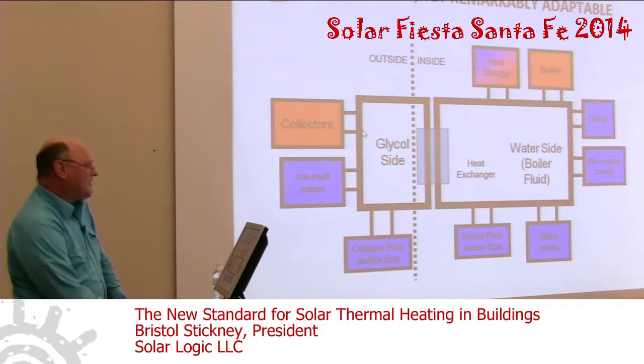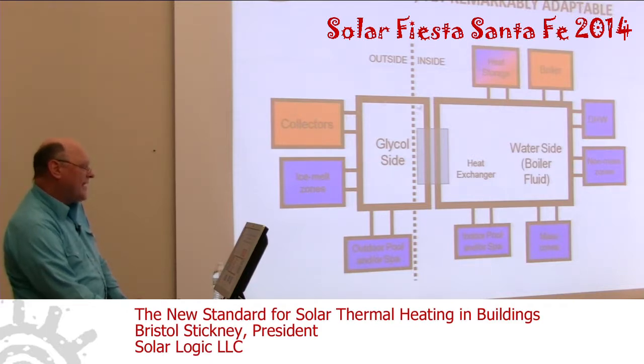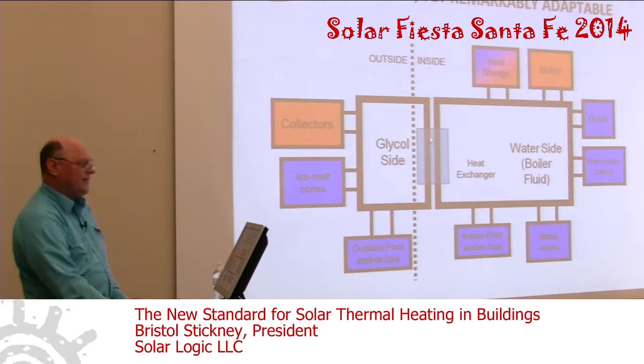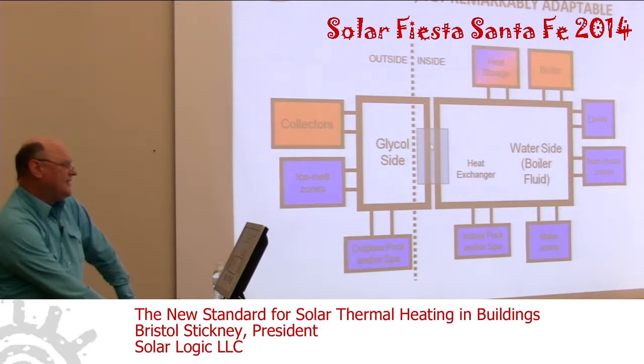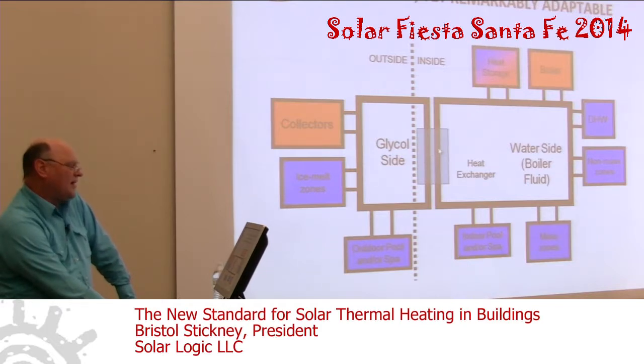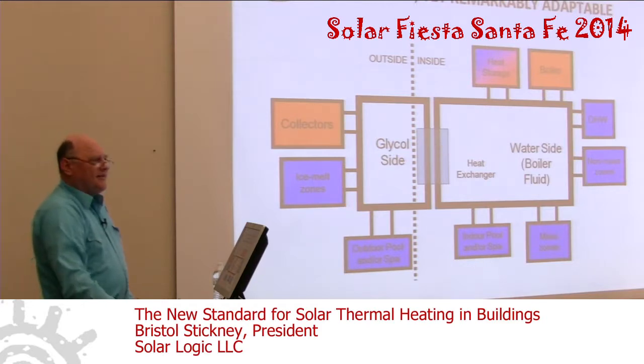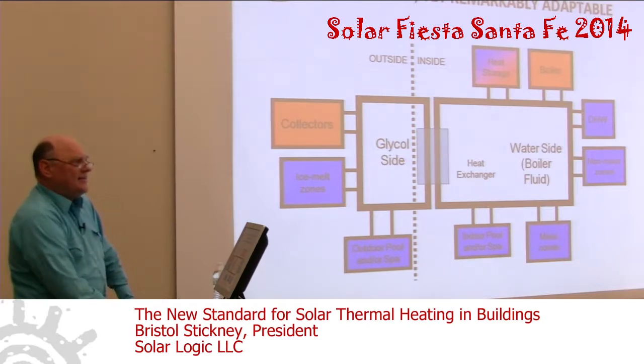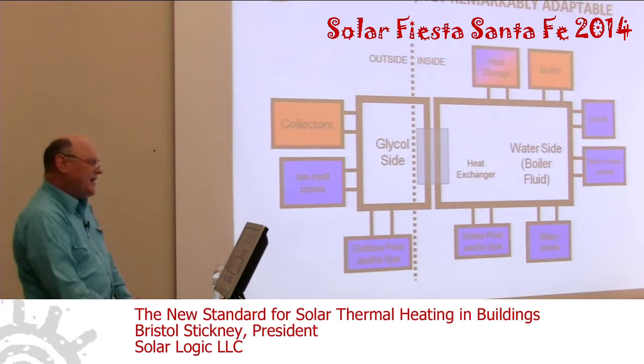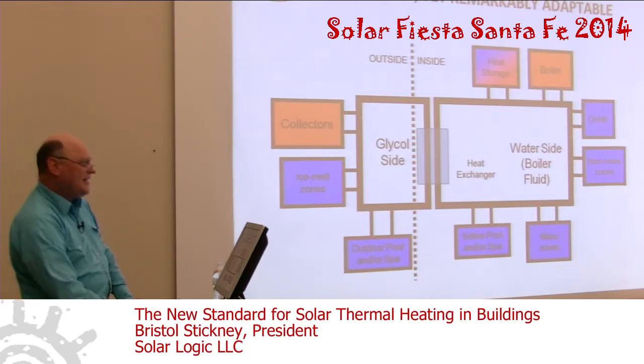So here's how it works. The sun comes up, the collector gets hot, a pump turns on and pumps heat through these collectors. The heat comes out, is pumped around back indoors to where the main primary loop for the house is. There's a heat exchanger that exchanges the heat from the glycol into the water, and then the control system realizes that there is heat available, decides that it's hot enough to do a real heating job, and turns on a heating job. And so somewhere around this primary loop, a heating job turns on when heat is available.